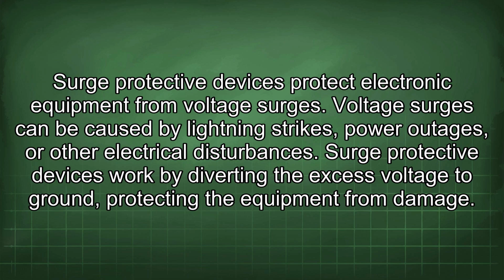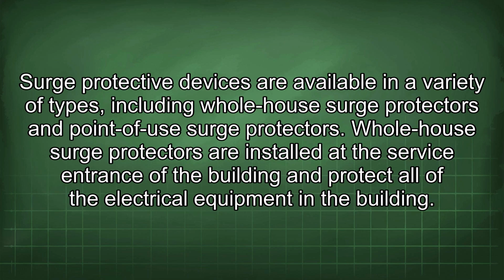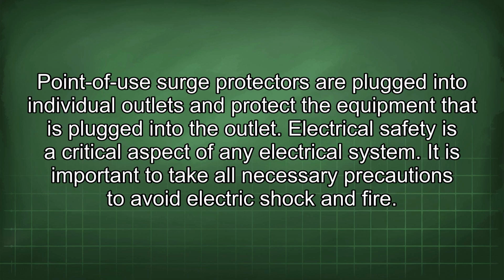Voltage surges can be caused by lightning strikes, power outages, or other electrical disturbances. Surge protective devices work by diverting the excess voltage to ground, protecting the equipment from damage. Surge protective devices are available in a variety of types, including whole house surge protectors and point of use surge protectors. Whole house surge protectors are installed at the service entrance of the building and protect all of the electrical equipment in the building. Point of use surge protectors are plugged into individual outlets and protect the equipment that is plugged into the outlet.